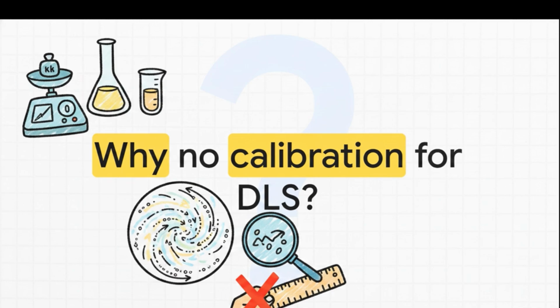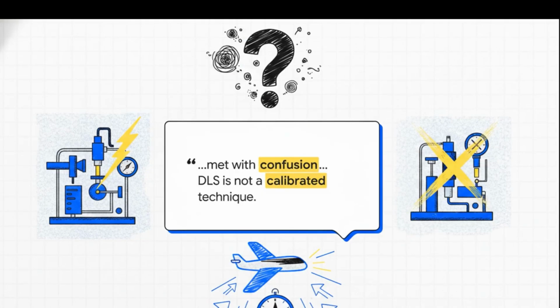Honestly, it feels incredibly counterintuitive. In almost every other analytical technique, calibration is the literal bedrock of accuracy. You weigh a known standard, you zero the scale. But DLS completely flips this script. There's a quote directly from Brookhaven Instruments that captures that sheer disbelief perfectly. They say, "At times we are met with confusion when we state there is no calibration and that DLS is not a calibrated technique." And it's totally understandable why folks are shocked to discover their advanced instruments are officially uncalibrated. It kind of feels like flying blind. But as we're going to see, it's actually the exact opposite.